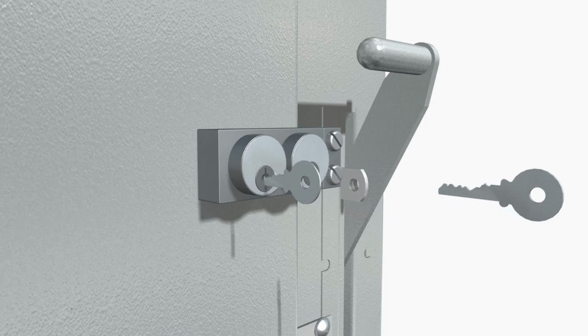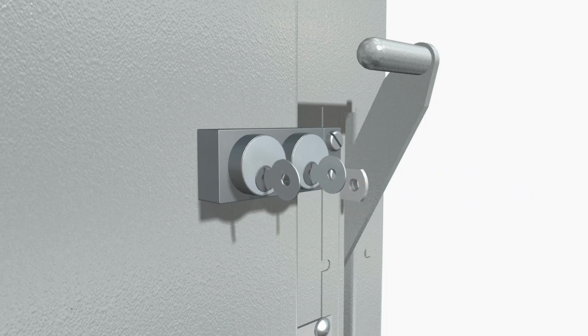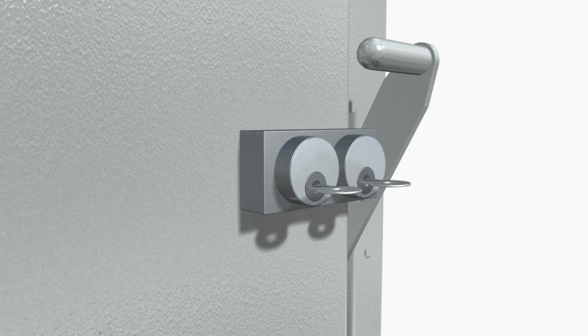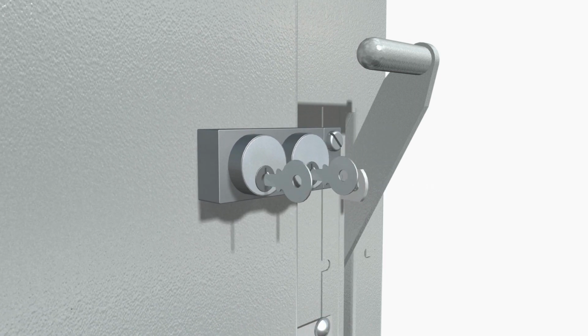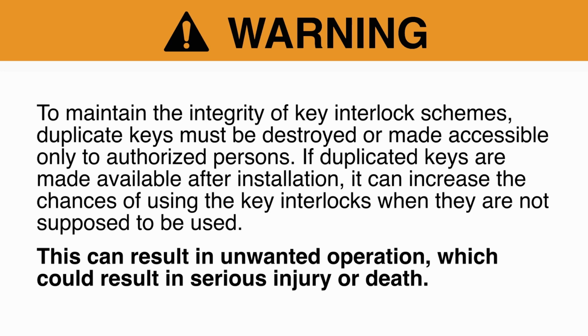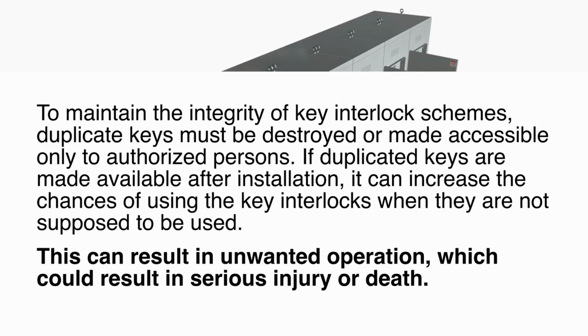Step 23. Check the functional operation of the key and mechanical interlocks if furnished. Warning: to maintain the integrity of key interlock schemes, duplicate keys must be destroyed or made accessible only to authorized persons. If duplicated keys are made available after installation, it can increase the chances of using the key interlocks when they are not supposed to be used. This can result in unwanted operation, which could result in serious injury or death.